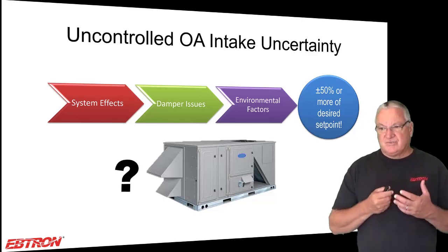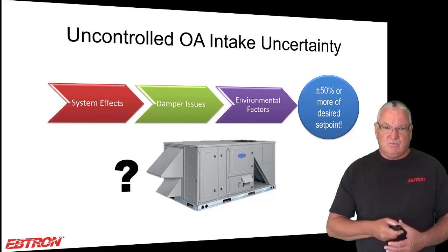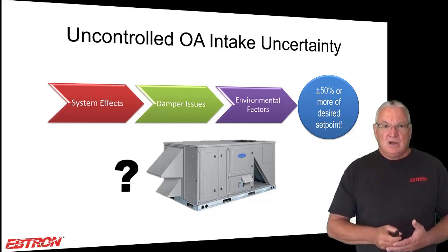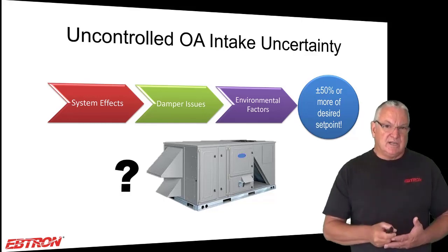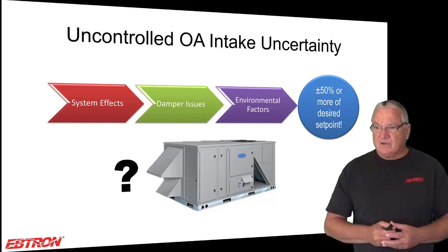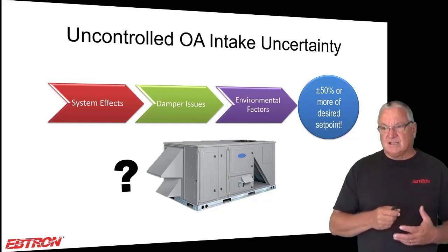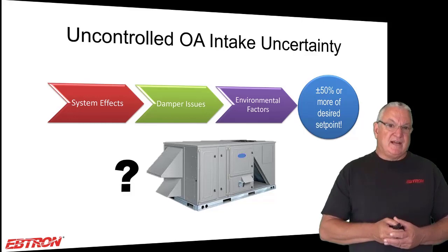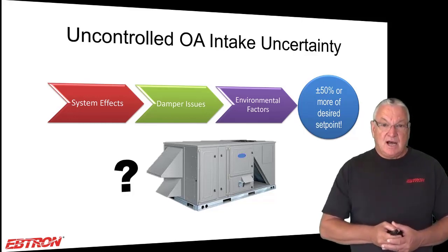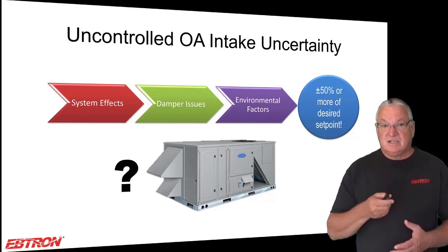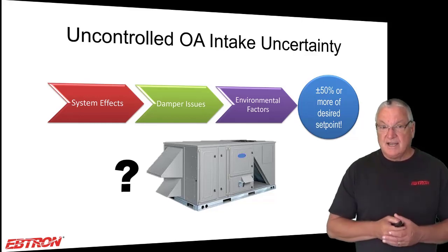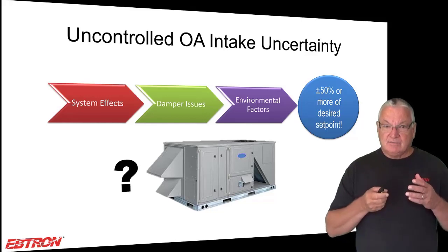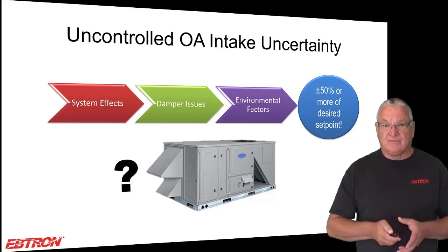And it's not just recirculating air systems. We have these wind pressure problems and stack pressure problems on DOAS. We have filter loading on DOAS. We have DOAS systems serving multi-speed fan coils in some cases. I just use this because this is the worst case. And I want to just point out that you have to somehow control outdoor airflow rates.